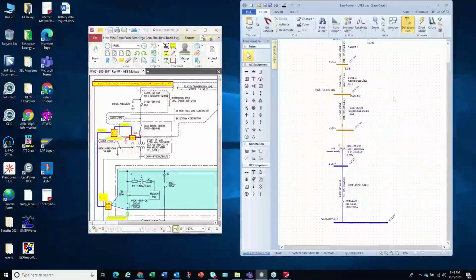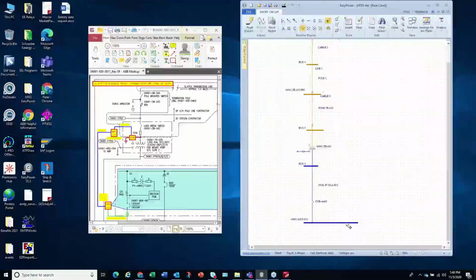Then we go to short circuit again and fault it, and you'll see we get 0.2 calories on both the 480 volt bus and on the line side of the main breaker. And once this happens, now what we don't see is that your primary fuses are going to blow, and so your transformer will be de-energized right away.